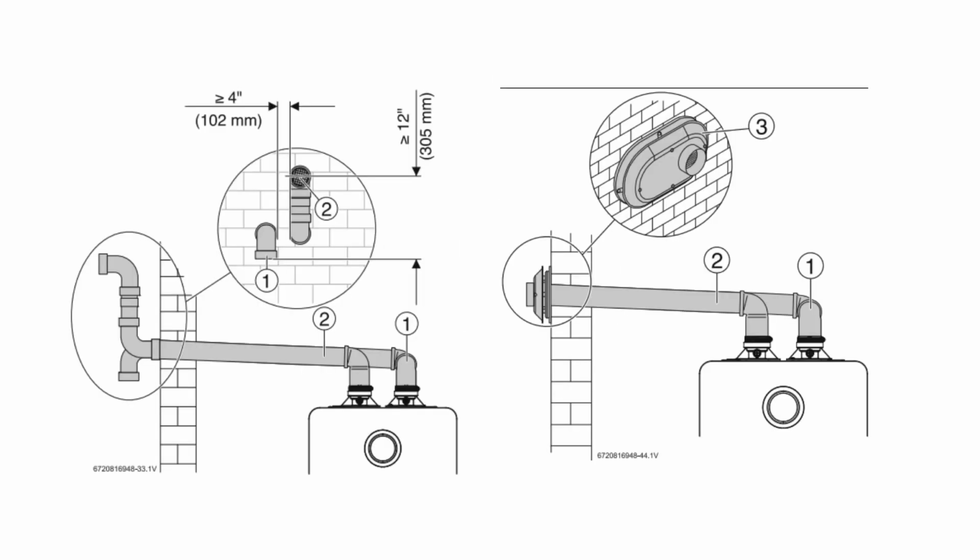If this doesn't correct the error code, check the air opening and exhaust opening for obstructions and reset the error. Then check if the flue length is according to the specifications under section 4.6 in the installation manual and reset the error.